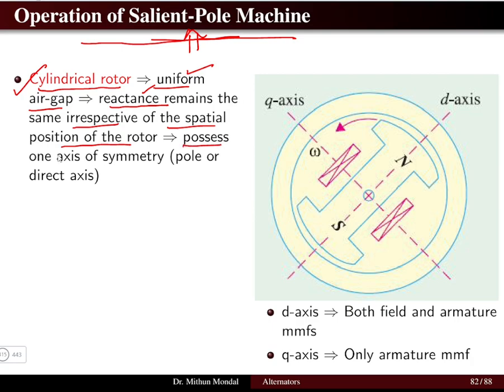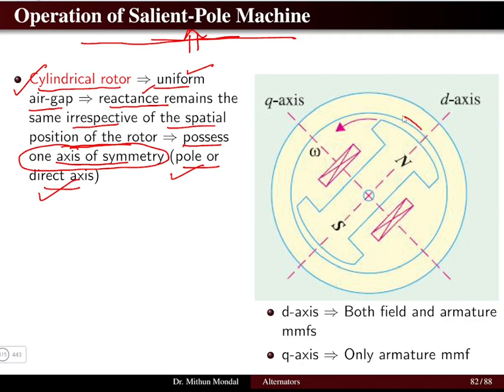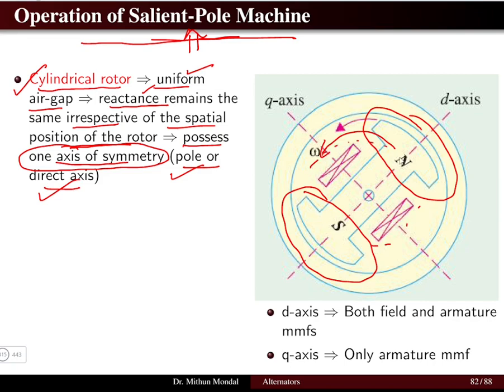The cylindrical rotor possesses one axis of symmetry — that is the pole or the direct axis. Since the cylindrical rotor has a uniform air gap and reactance remains the same, only one axis of symmetry exists. However, this is not the same for the salient pole machine. In a salient pole machine, the pole projects out, and as the rotor rotates, the air gap flux is not uniform, so the reactance is not the same. We therefore deal with two different axes of symmetry: the d-axis and the q-axis.